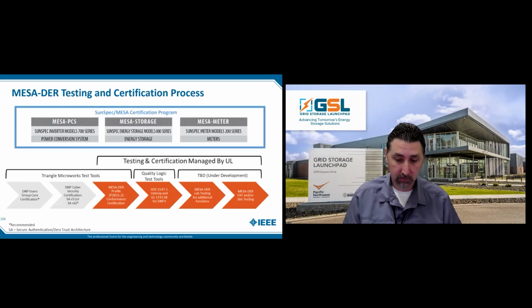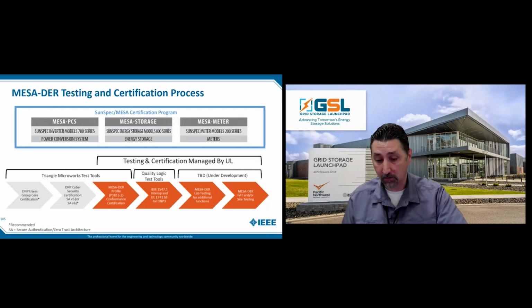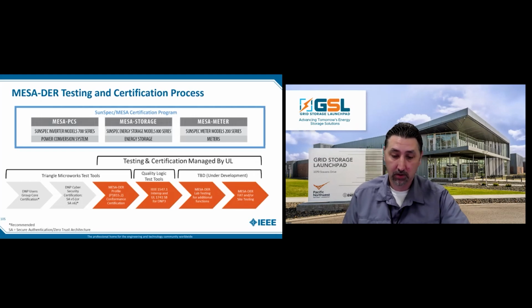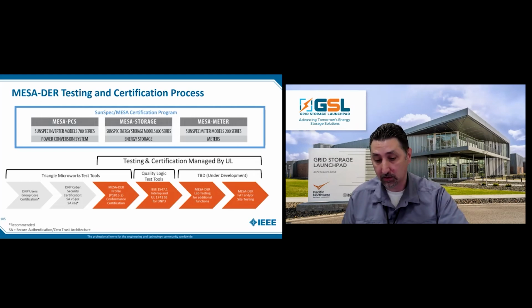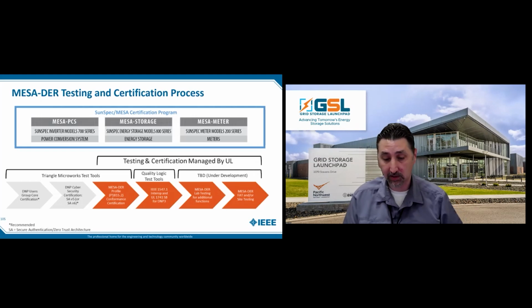In the final stage, you have factory acceptance testing. If you don't define factory acceptance testing in your procurement language, you miss a lot of these other things, because the factory acceptance testing or site testing that a vendor is going to do will be minimum. If you want to make sure they meet all your requirements, you have to specify the factory acceptance testing.